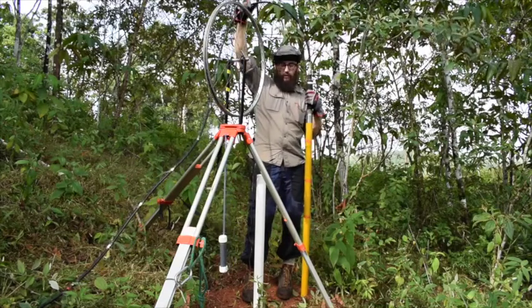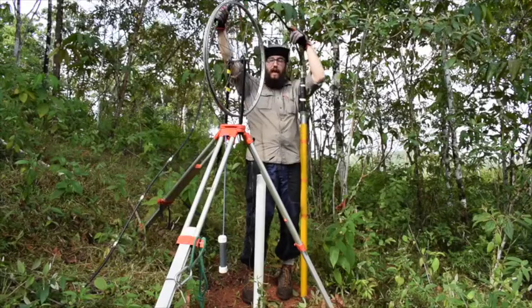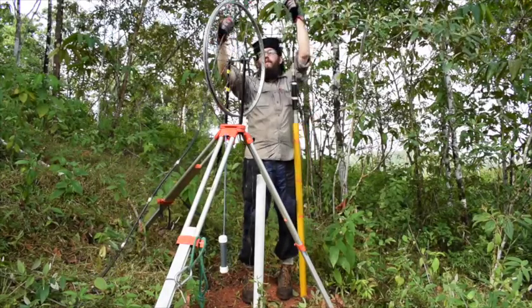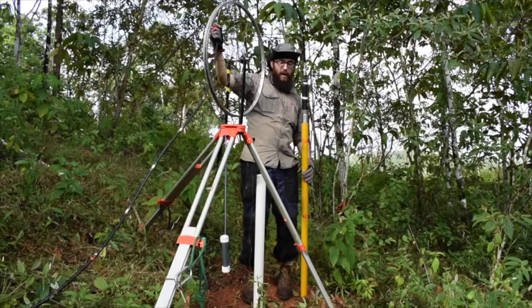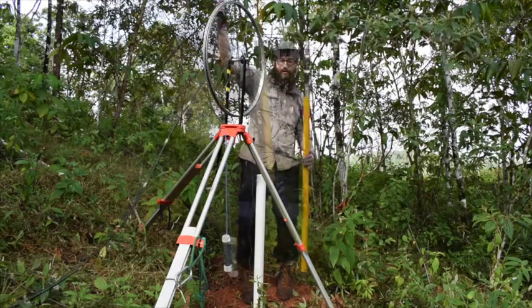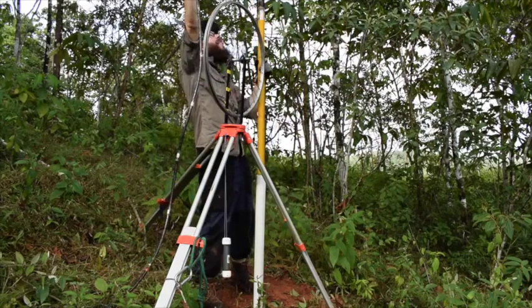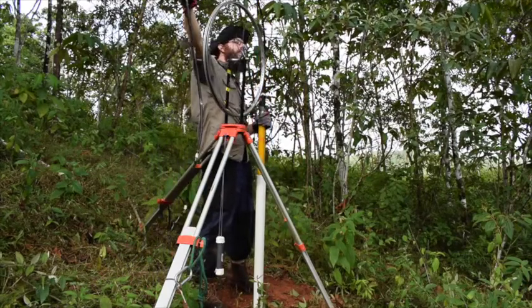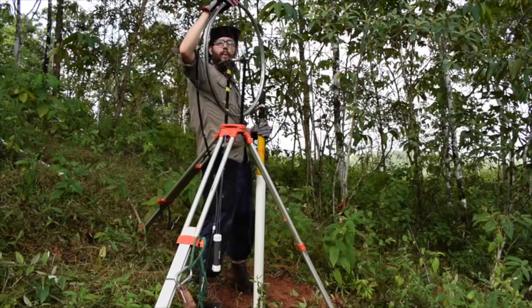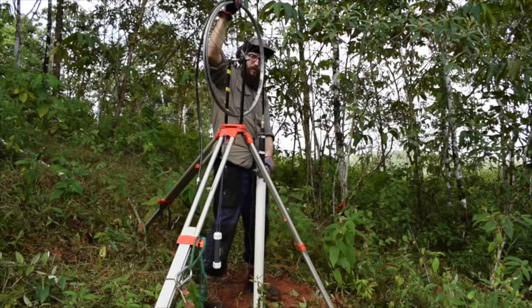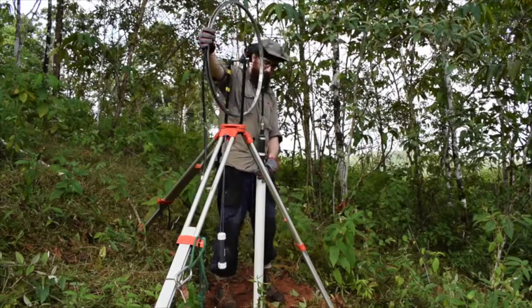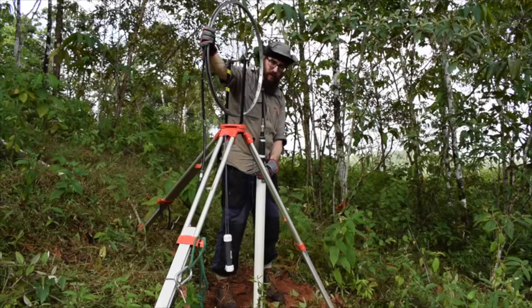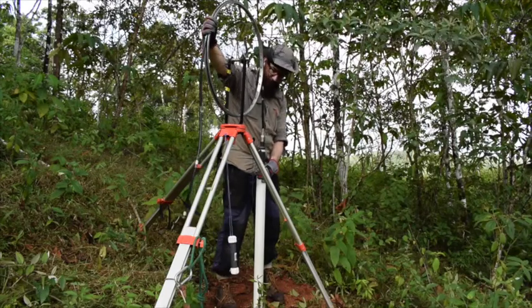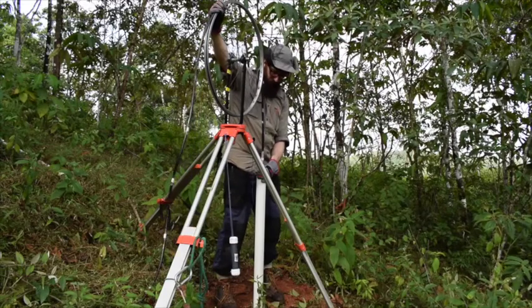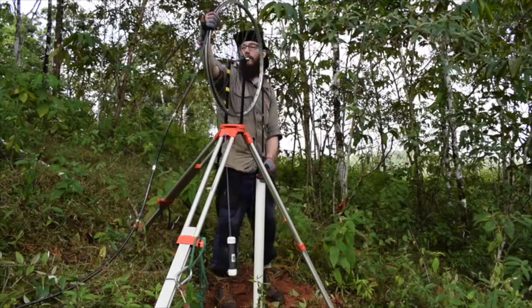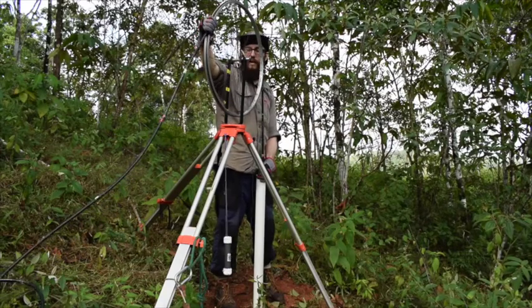So what I typically do, either with 2 people or 1 person, can do this with a hand above their head. Just always keep the length of wire right above the probe head up in the air. Now at this point, of course, if you were to let it go, gravity would take the probe to the bottom of the well, so we want to be really careful. Again, this is a job that's handy to have 2 people for, but as long as you keep friction on the cable as you let it slowly down.